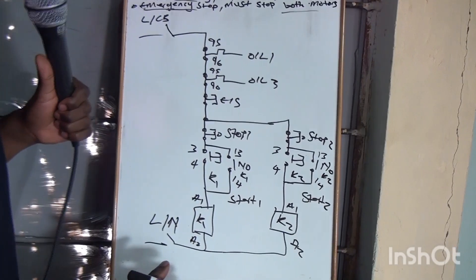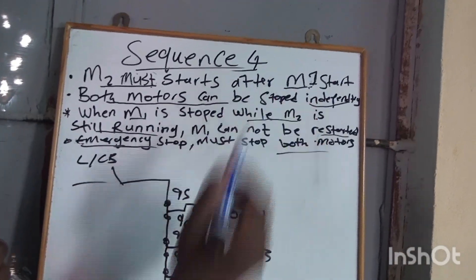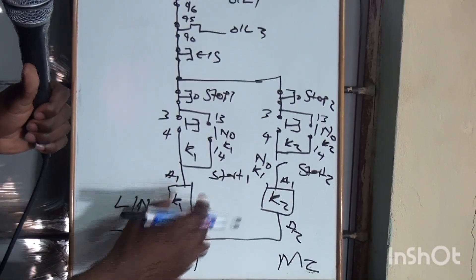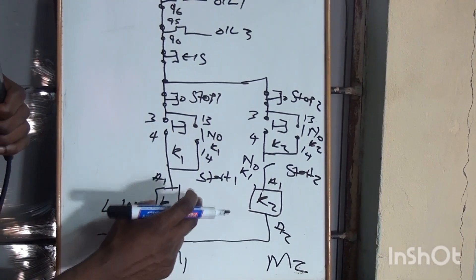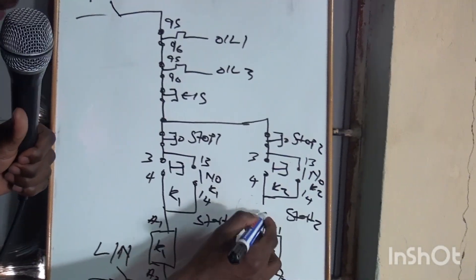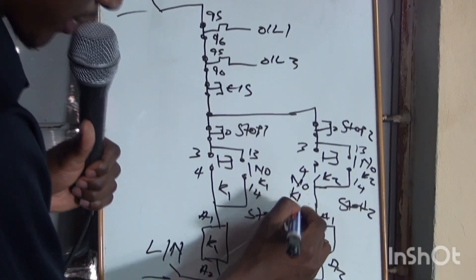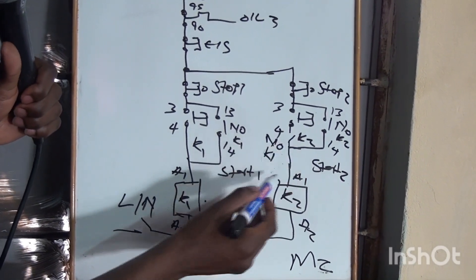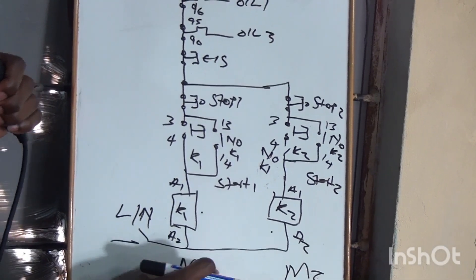This is the direct online for both sides. This side is for Motor 2 and that side is for Motor 1. The first statement says Motor 2 must start after Motor 1. So what we do is introduce a normally open contact of K1 on the Motor 2 side. When the K1 coil energizes, this normally open becomes normally closed, allowing you to start Motor 2. If you stop Motor 1, Motor 2 won't stop, and if you stop Motor 2, Motor 1 won't stop — they are independent.